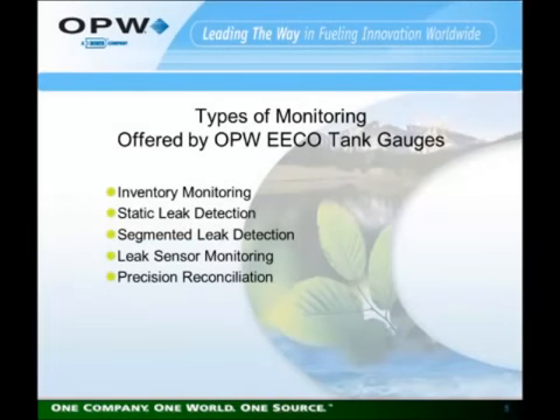The types of monitoring offered by the OPW EECO gauges are inventory monitoring, static leak detection, segmented leak detection, leak sensor monitoring, precision reconciliation, and if one of the EECO tank gauges is interfaced to the Incon TS LS300 pressurized line leak system, it will operate as an interface to that system to supply pressurized line leak detection on pressurized product piping.